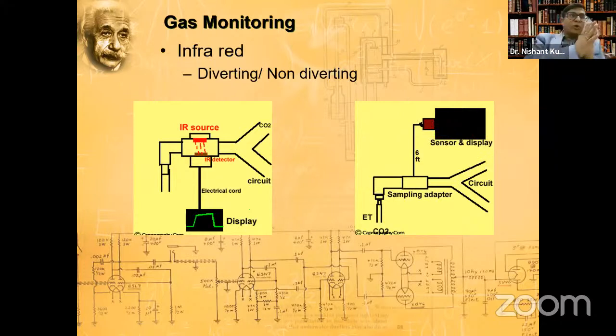But if you go to some older monitors, they will say whether you're using nitrous oxide or not. And if you're using nitrous oxide, what is the percentage of oxygen that you're using, so that it decides how much nitrous oxide is being used and it applies a correction to the CO2. So if you feel that your PaCO2, EtCO2 is not matching, please look at your monitor in the settings, go to the EtCO2 settings and see whether you have set this, whether your monitor requires it to be set for nitrous oxide correction or not. Okay, that is very important in some of the monitors, the older ones specifically.